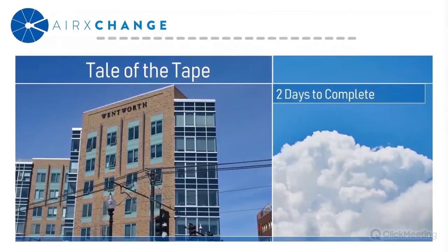So what made this project so successful? Well, one of the things is that on this project, we actually were able to offer better performance. We offered a wheel at a lower pressure drop than the original, which is great because it gives them some additional fan savings, as well as a higher efficiency operating device. So they're getting more sensible performance out of the device.